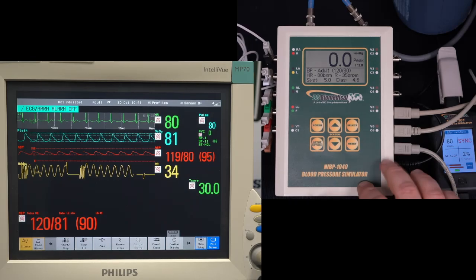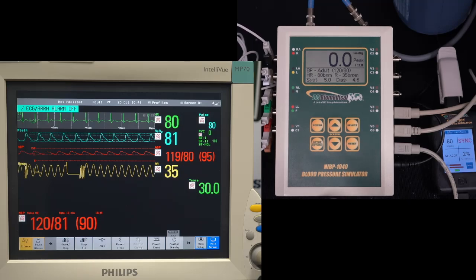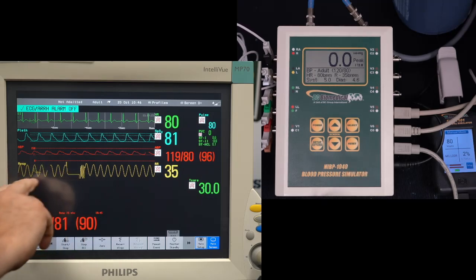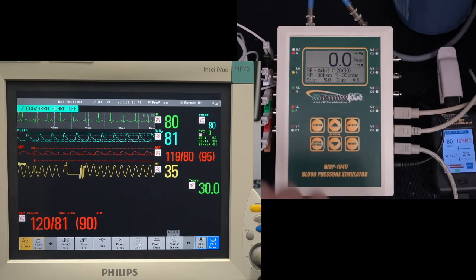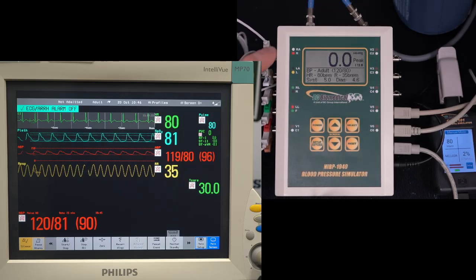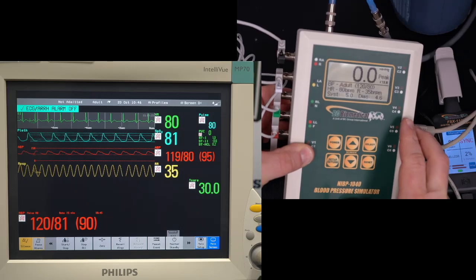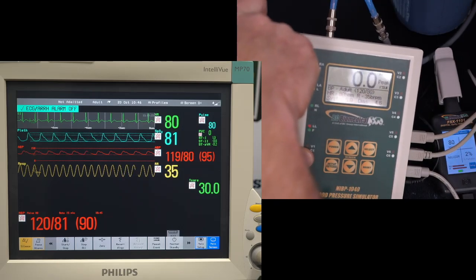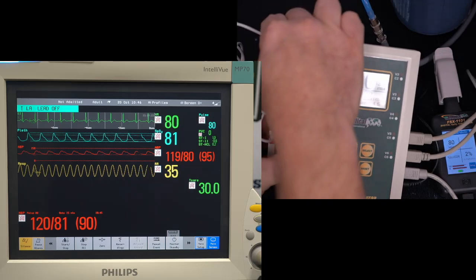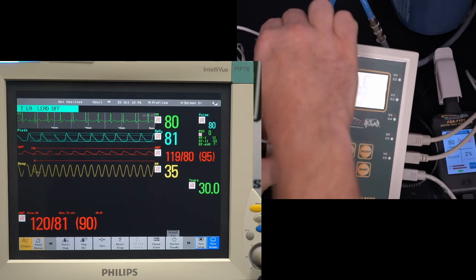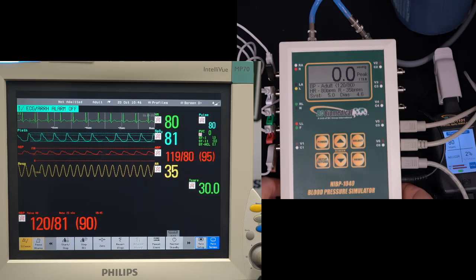Now our patient simulator, the PS2240, 2200 series, you can adjust which lead the respiration is in, whether it's in the left arm or the left leg. But the NIBP can't. So when we want our respiration to be simulated and measured, we have to make sure we connect the leads to the proper connection on there. Now the other thing I'll point out is the NIBP-1040. This has the extended lead connections on the side. So this allows me, you can kind of see the hole here, so I can either plug in a banana jack into that hole or the pin, or I can clip onto the side with my test snap there.